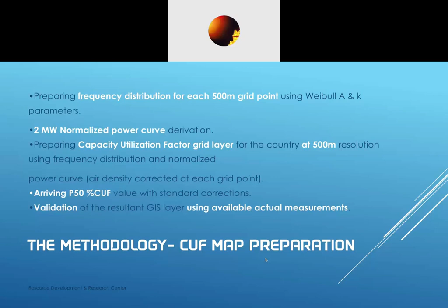Power curves are corrected as per IEC standards, and then they arrive at the P50 CUF value with the standard corrections. Then the results are validated with the GIS layer using available actual measurements. So they did not simply rely on the data sets. They validated these results with the actual measurements they have for various locations. Cumulatively, up to now, NIWE has 877 mast data from their end. For this estimation, I think they used around 400 plus met masts for validation purposes. This is a good number for getting accurate results.